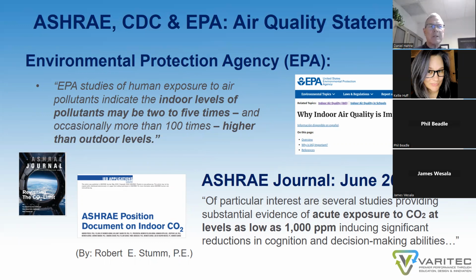And there's another component that's gaining national attention as well, and that is CO2 contaminant levels. How much CO2 is in a building? ASHRAE has always advocated for 1,000 parts per million of CO2 per cubic foot of air. However, we're finding out now that outdoor CO2 concentrations have increased from about 360 to 380 parts per million as measured back in the 1980s, to now measuring in the range of 500 to 600 parts per million here in downtown Phoenix, Arizona, and in Los Angeles from 600 to 700.